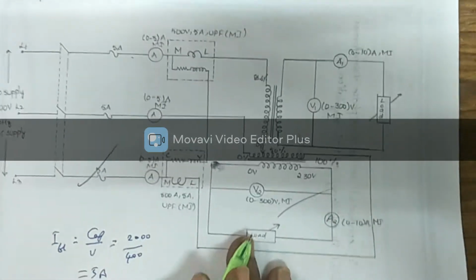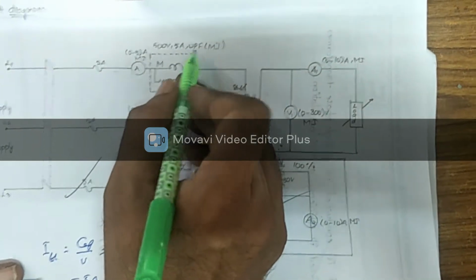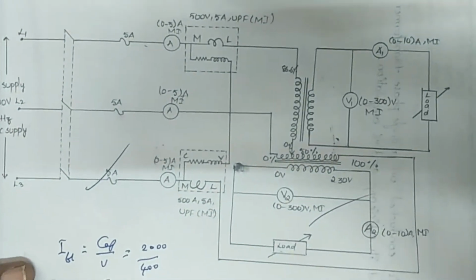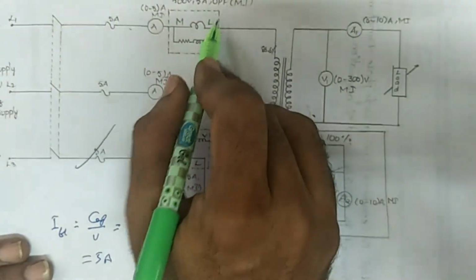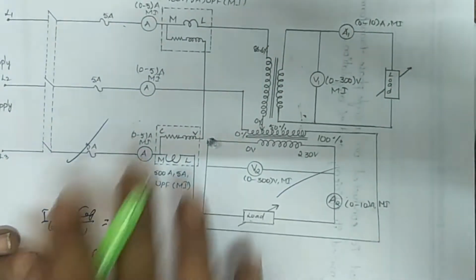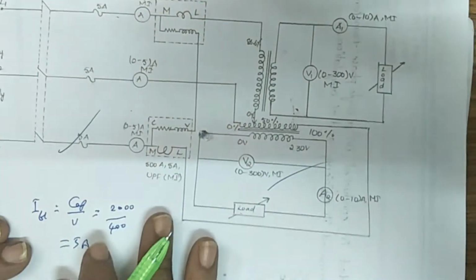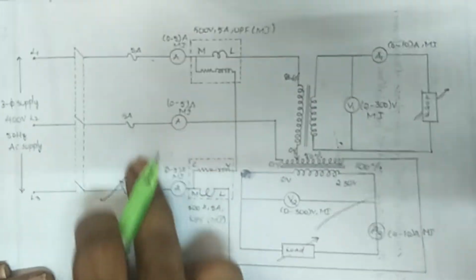Since this experiment is conducted under load condition, definitely you need to consider unity power factor, because as the load on the transformers is increasing, the power factor will be increasing. So definitely unity power factor wattmeters are to be considered. And of course wattmeters are of electrodynamometer type. This is about the ratings of ammeters and wattmeters on the primary side.